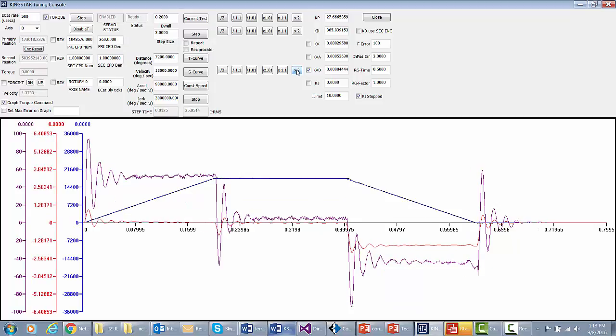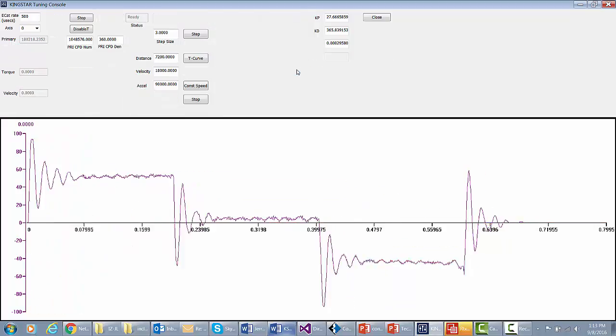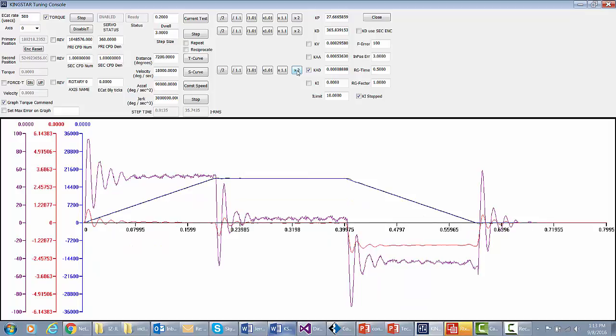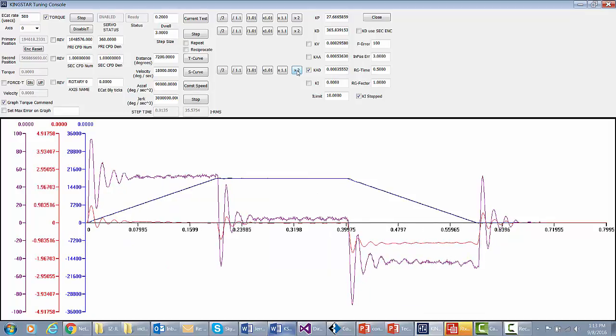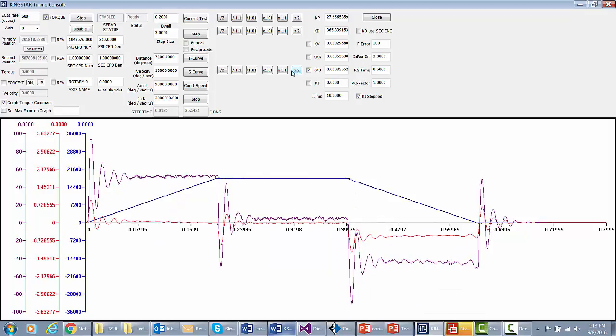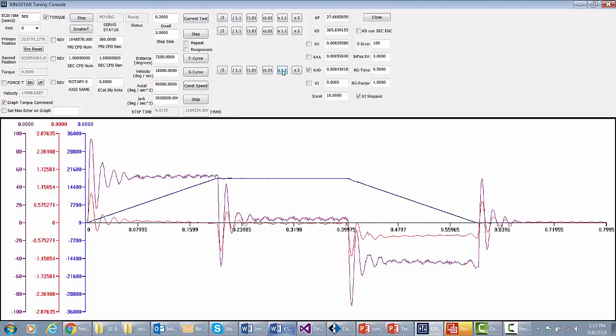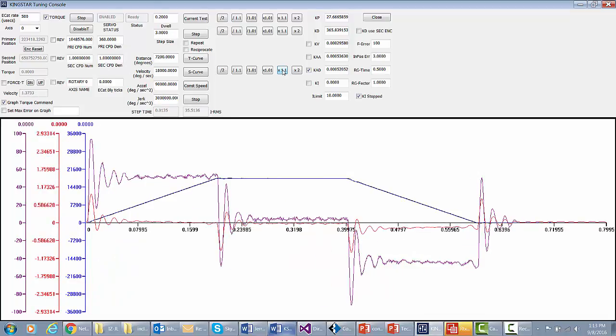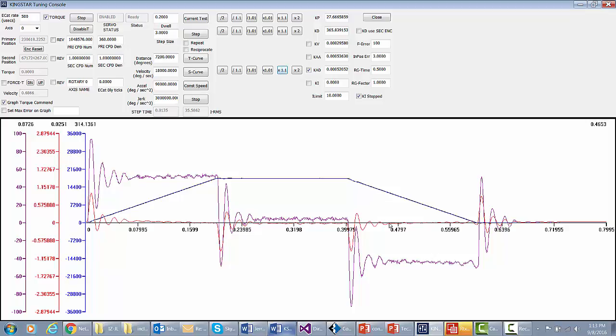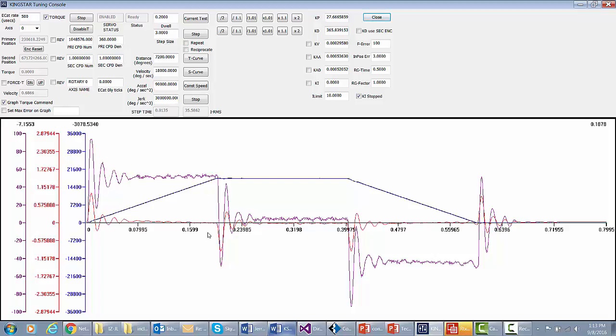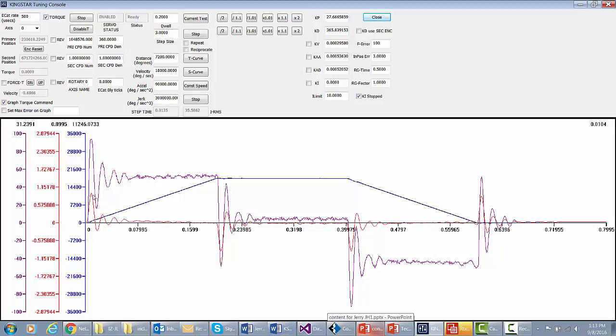So again, we're going to do these separately, and up it comes. Now once this starts to move, it goes pretty quick, so I'll just go up by 10%. I can just do a couple of these. We're in the ballpark right there. Now at this point, you can see this is quite a spike that we need, and if you can hear this motor, there's a little bit of vibration there. You can hear these serious peaks, and the total error right now is 0.9 degrees.